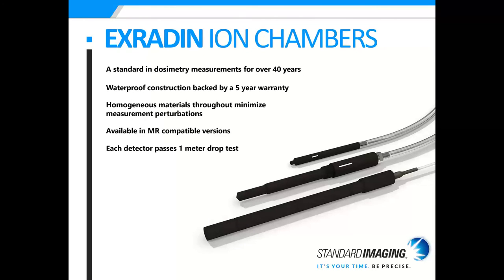Our EXRADIN ion chambers have been a standard in the dosimetry field for over 40 years. They feature waterproof construction backed by a five-year warranty. The homogenous materials throughout minimize measurement perturbations, and many chambers are available in MR-compatible versions. Each detector also passes a one-meter drop test, so they are very durable.